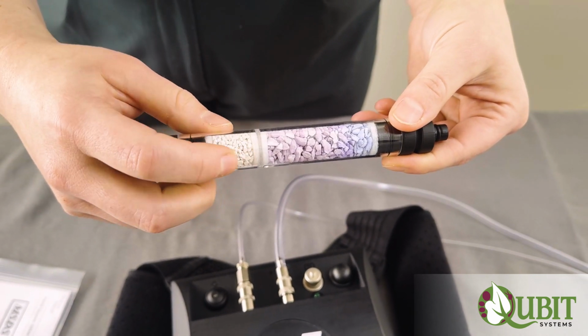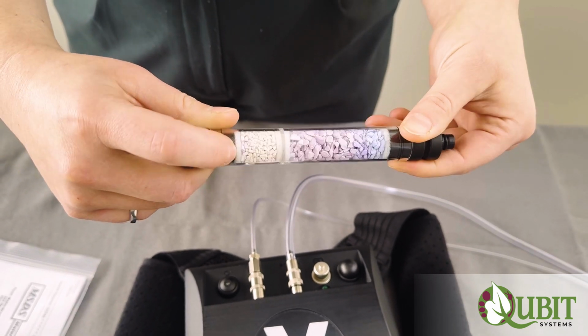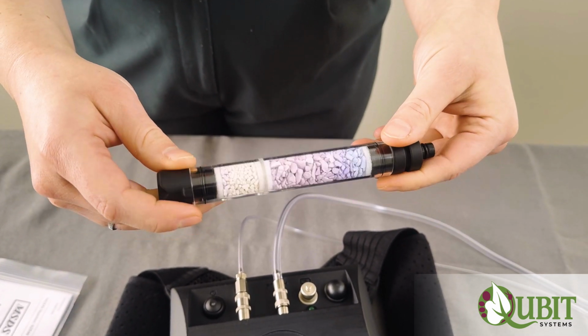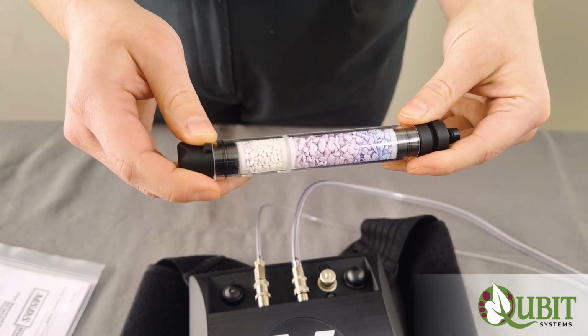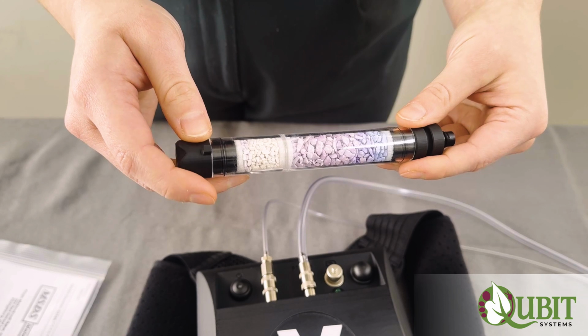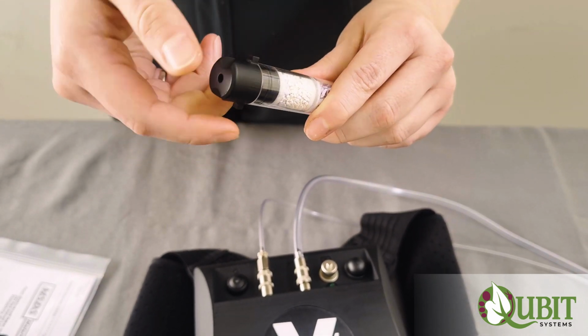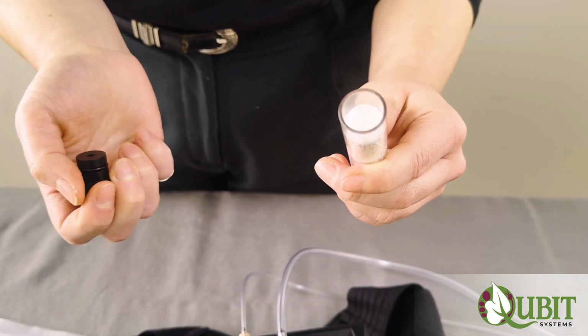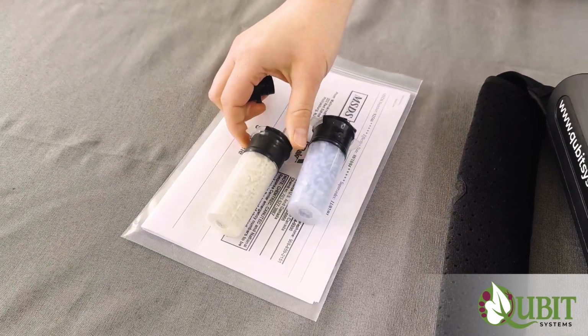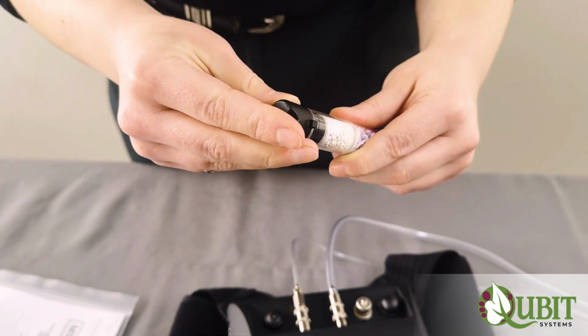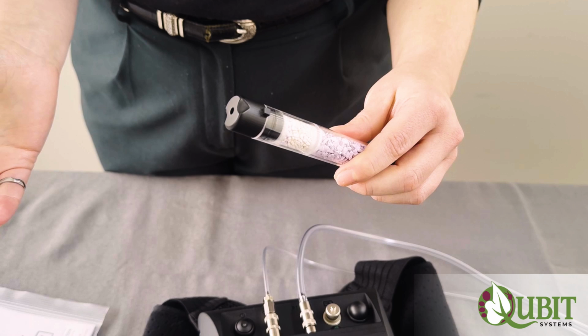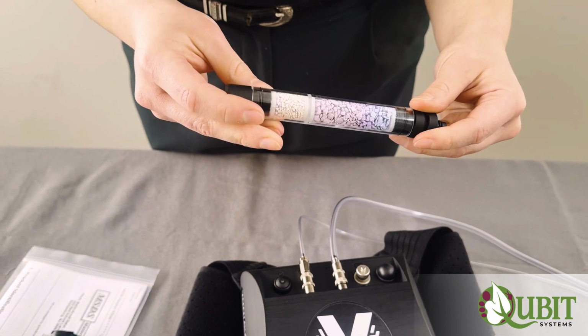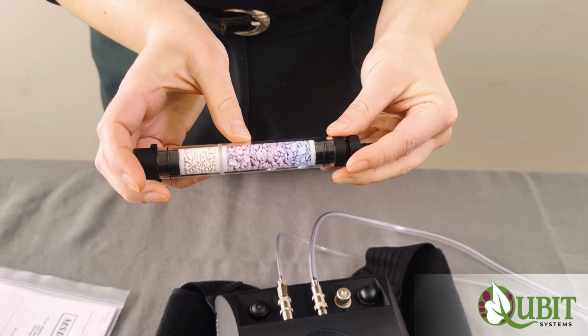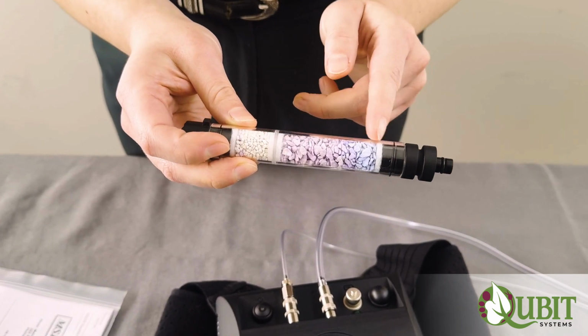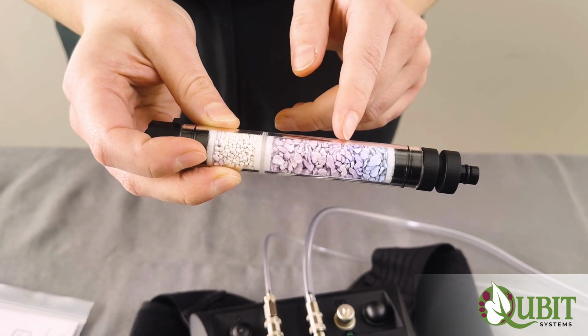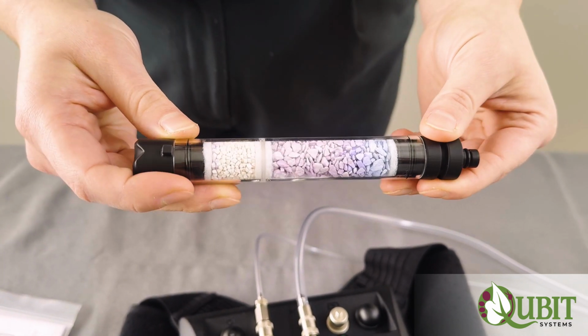As soon as you notice that the majority of the soda lime is purple, or that there's a purple line at the bottom of the soda lime column, it's important to replace the soda lime as soon as possible, because this purple indicator can fade over time. So to replace the soda lime, you would remove the end cap, remove the filter, and the VOCO package is supplied with extra chemicals, so you would use the extra soda lime and replace it there, and then dispose of the expired soda lime using the instructions on the material safety data sheets provided. In contrast, the Drierite pictured here turns first a bright purple and then a pink color when it expires.